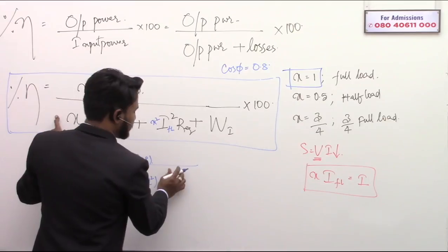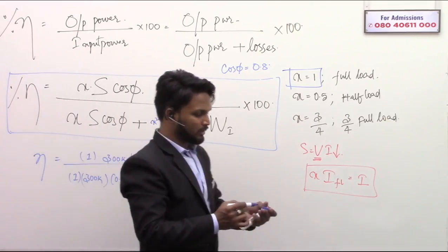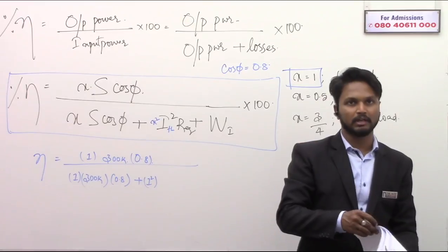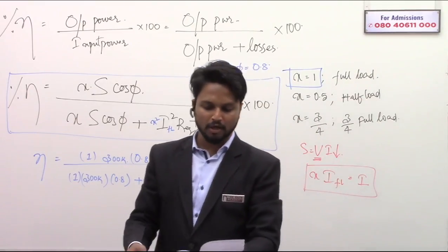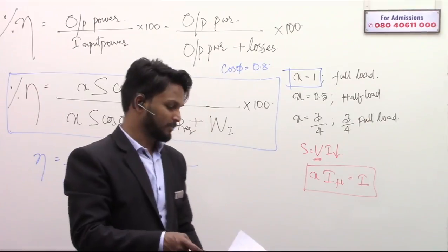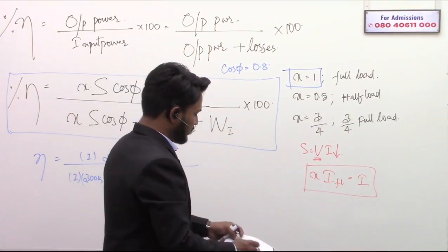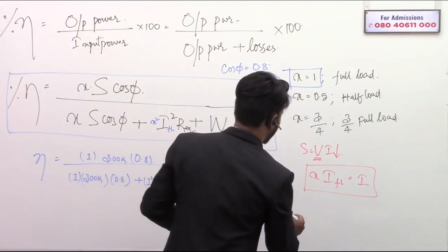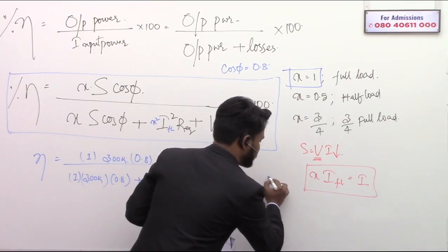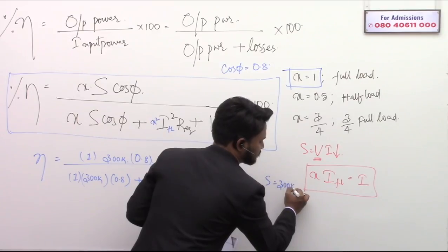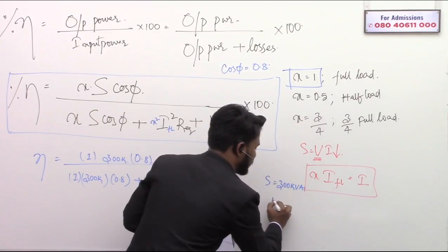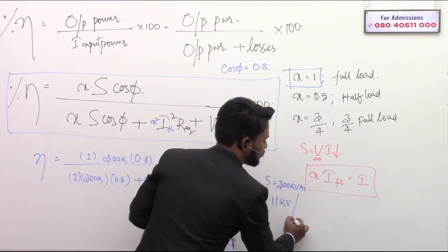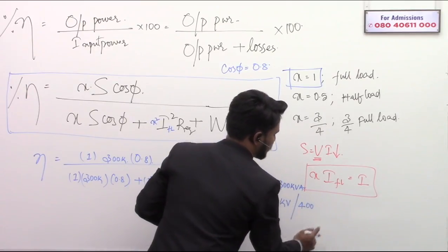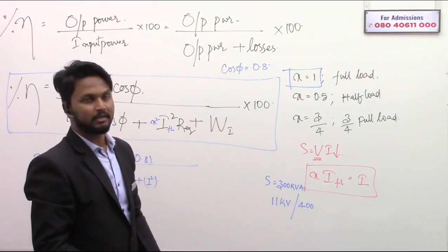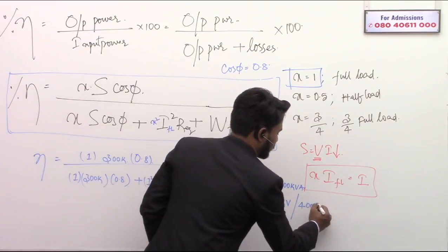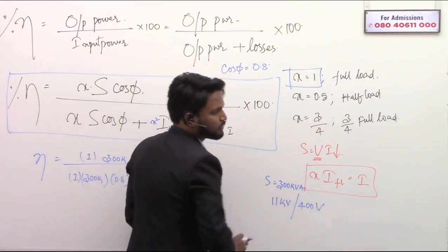current. See, the full load current, in the question they have mentioned the actual full load current. Or else, if the full load current is not mentioned, you have to find it out. The voltage ratings of the transformer are given like this. It is a 300 kVA transformer and the voltage ratings are 11 kV by 400 volts. Yes, 11 kV on the HV side and 400 volts on the LV side.